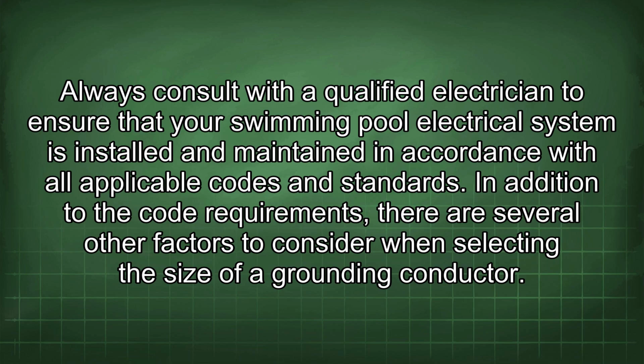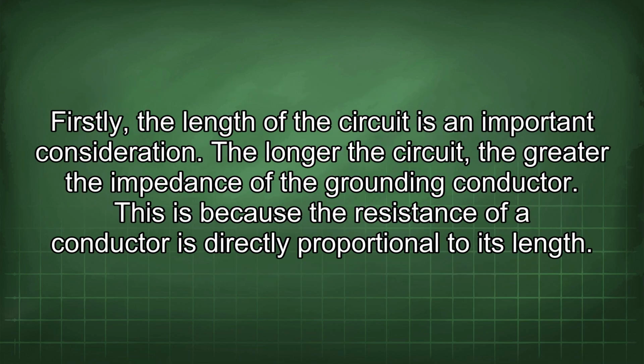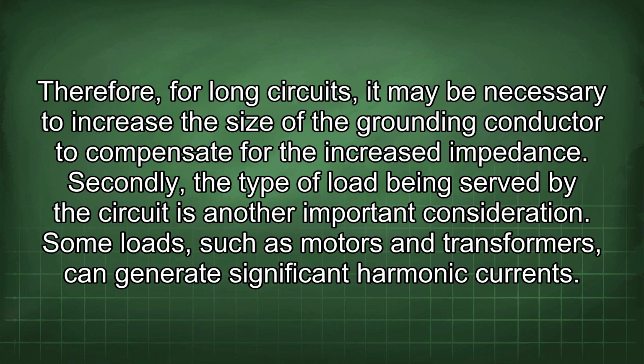In addition to the code requirements, there are several other factors to consider when selecting the size of a grounding conductor. Firstly, the length of the circuit is an important consideration. The longer the circuit, the greater the impedance of the grounding conductor. This is because the resistance of a conductor is directly proportional to its length. Therefore, for long circuits, it may be necessary to increase the size of the grounding conductor to compensate for the increased impedance. Secondly, the type of load being served by the circuit is another important consideration.